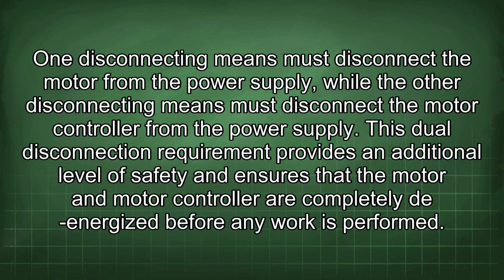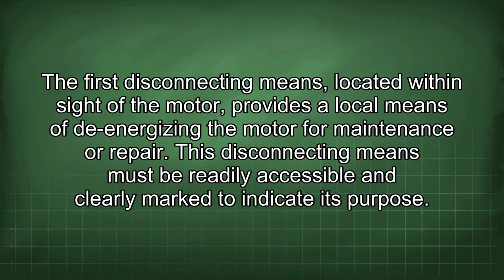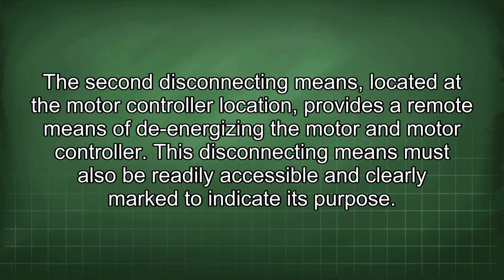This dual disconnection requirement provides an additional level of safety and ensures that the motor and motor controller are completely de-energized before any work is performed. The first disconnecting means, located within sight of the motor, provides a local means of de-energizing the motor for maintenance or repair. This disconnecting means must be readily accessible and clearly marked to indicate its purpose. The second disconnecting means, located at the motor controller location, provides a remote means of de-energizing the motor and motor controller. This disconnecting means must also be readily accessible and clearly marked to indicate its purpose.